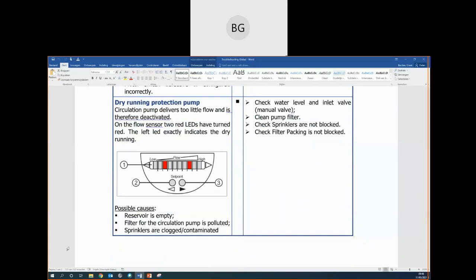Dry running circulation pump. If the circulation pump delivers too little flow, this is detected on the flow sensor. The two LEDs have turned red, and the left LED exactly indicates the dry running. This could be caused by the reservoir being empty, the processed water being empty. It could be due to the filter for the circulation pump being blocked, or due to the sprinklers being blocked. It could also be that the pin on the back of the sensor has developed a film on it.